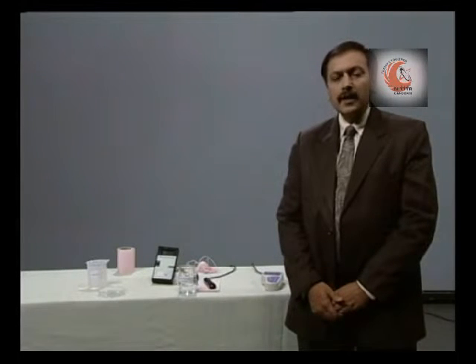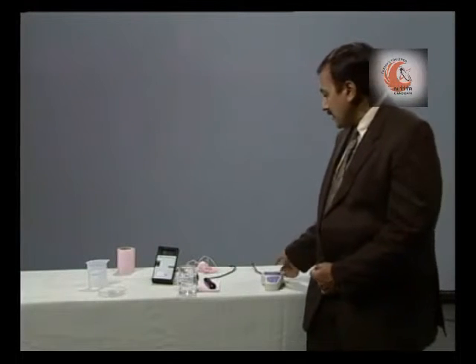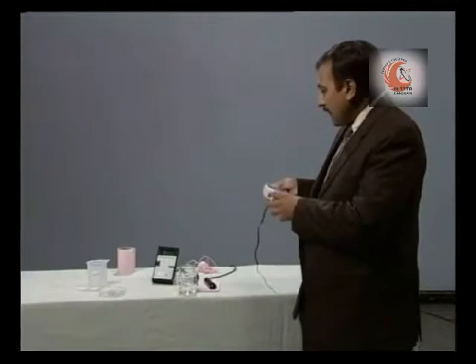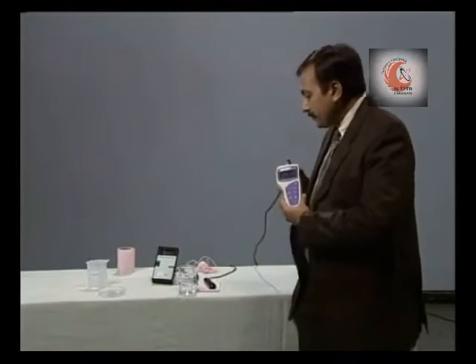The third calibration is carried out for DO values. This is done against a solution of known DO value. We will use deionized water for this purpose. The DO value for deionized water at 23.6 degree centigrade is 8.38. So we will adjust the same value on the instrument.